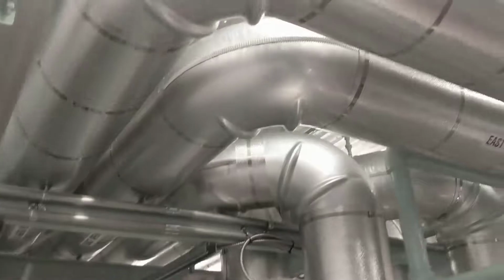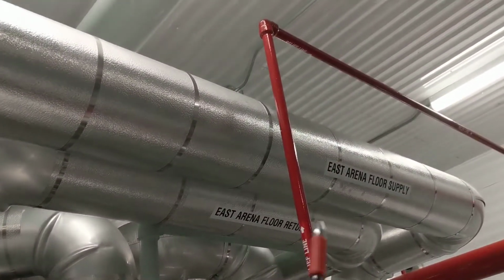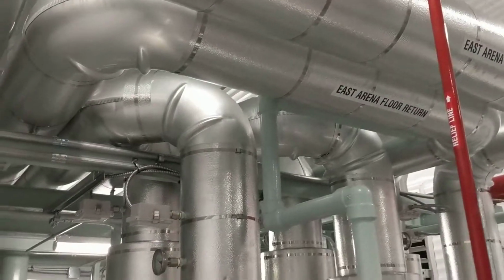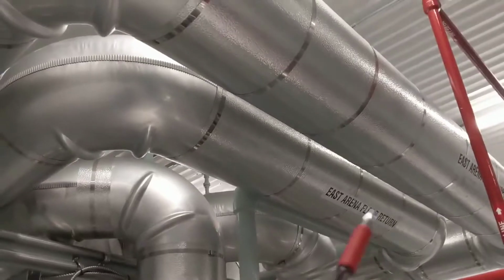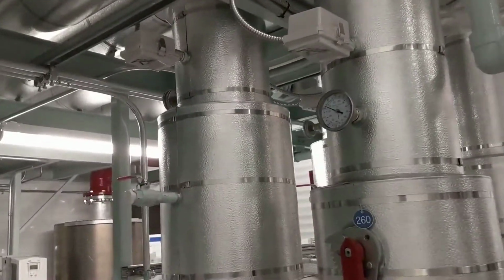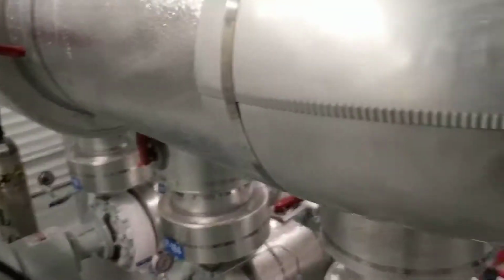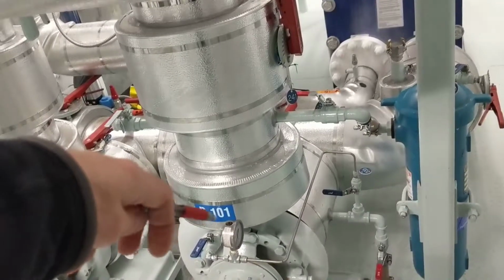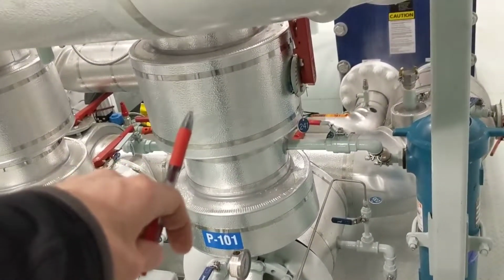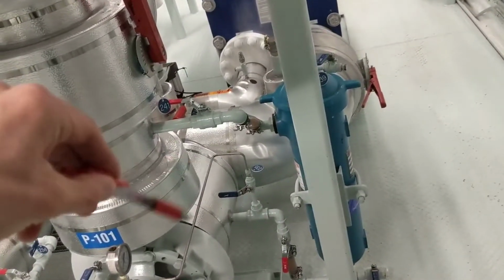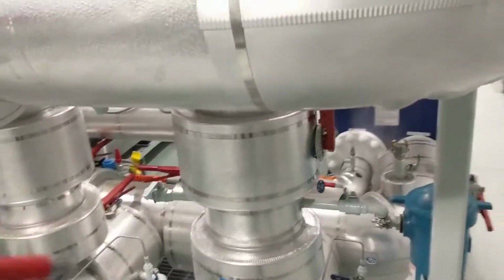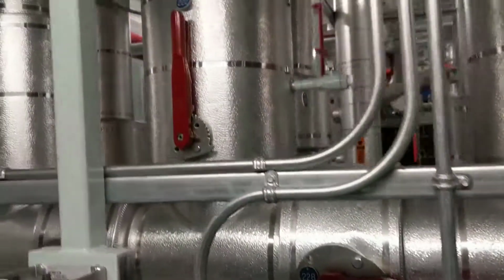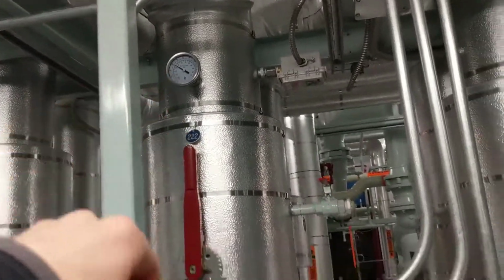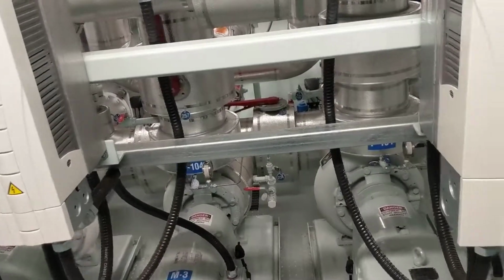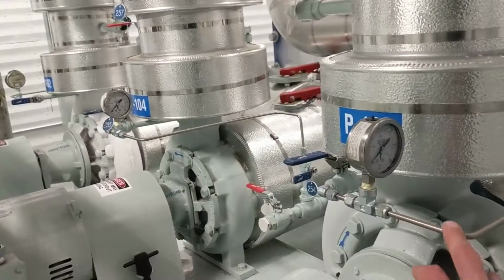In terms of labeling, you can see that there are labels out here. They couldn't really wrap the pipes with them because of the size of the labels, but if you trace them back, you'll be able to figure out which is which. The easy way to tell is with these pumps: the part going out of the top of the pump is the supply, and the part going into the pump is the return. All of your temperatures can be found fairly close to the pumps, and all of your pressures are found just off the volutes of the pumps.